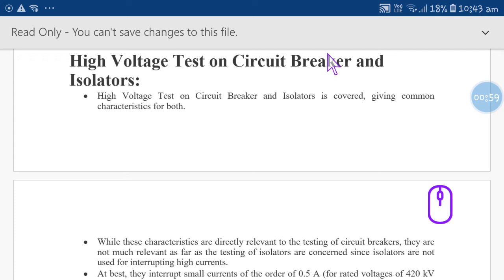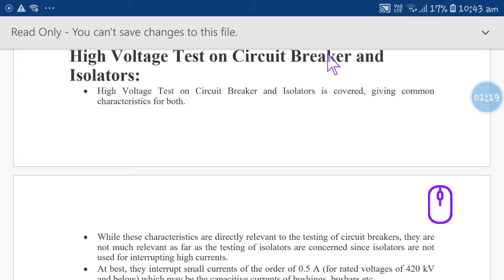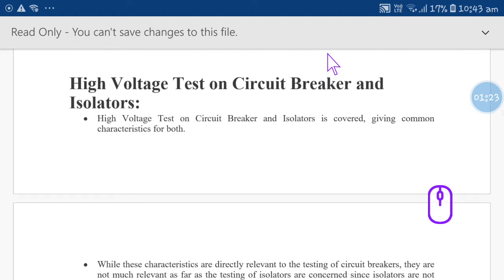The testing of circuit breakers as well as isolators is very important. Now, what is a circuit breaker? A circuit breaker operates under loading condition. Whenever a fault occurs, the relay has to sense it and the circuit breaker has to trip. Whereas isolators operate on no load. Isolators are provided on either side of the circuit breaker. First the circuit breaker has to operate, afterwards the isolator has to trip. This is the operation.